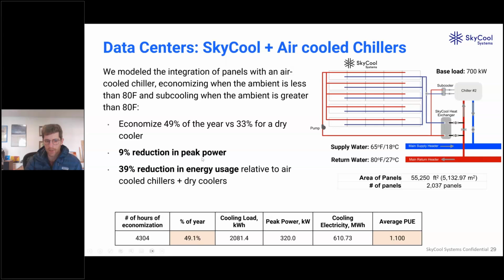We saw a 9% reduction in peak power. So this is going to be during those hottest hours of the year. The chiller was using 9% less power. And then over the entire year, a 39% reduction in energy use relative to the chillers. And that's really driven by reduction in fan energy and not using the chiller for a larger fraction of the time. And so you can see a summary table of the cooling load, how much power was used, and how much energy essentially was saved from cooling.